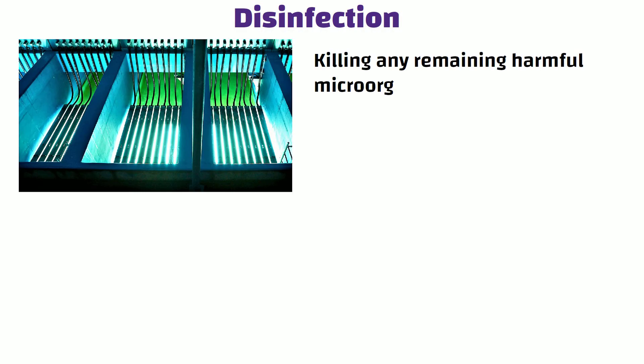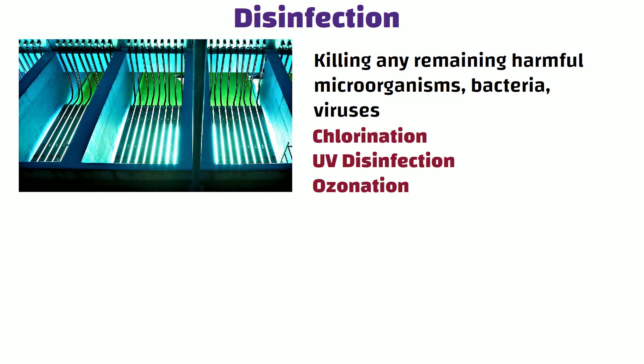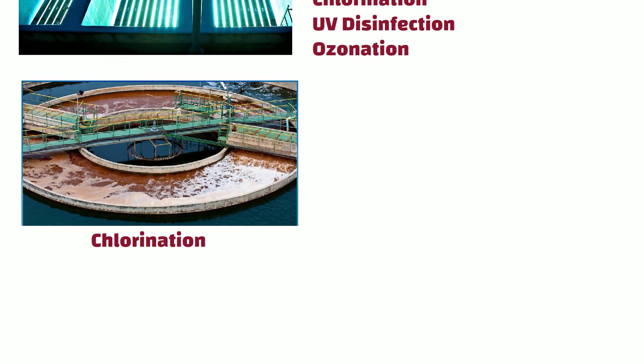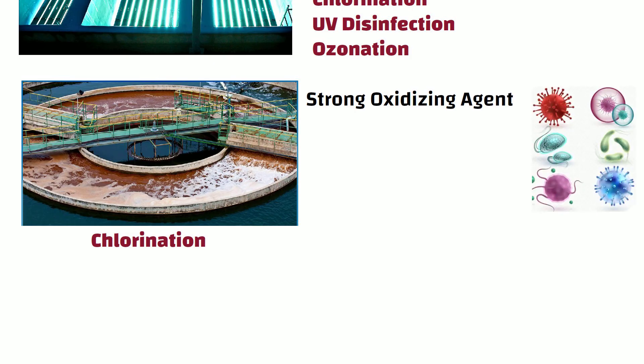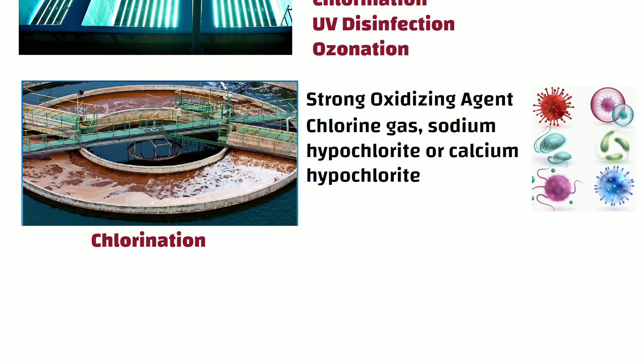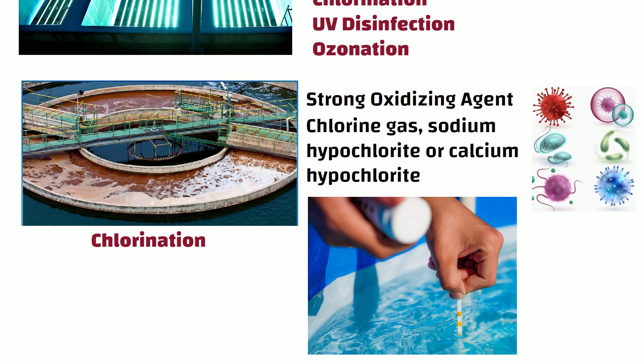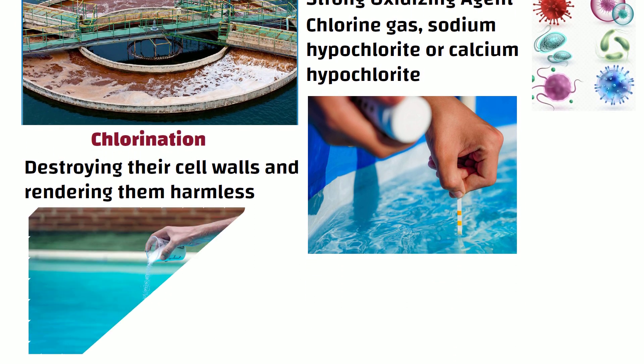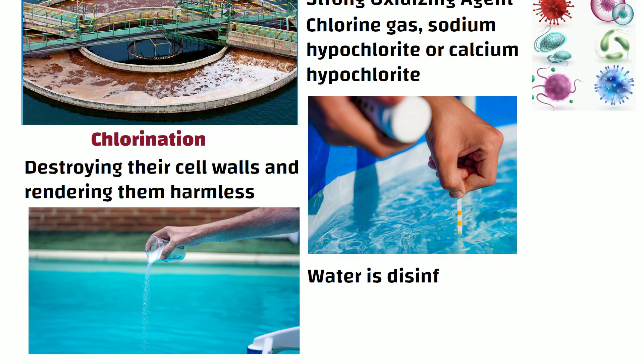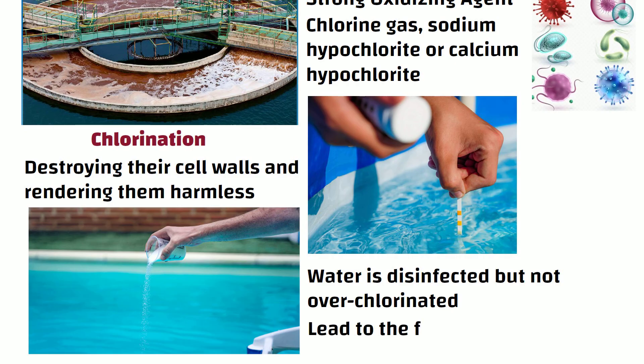Disinfection: this process involves killing any remaining harmful microorganisms, bacteria and viruses after filtration. The most commonly used methods are chlorination, UV disinfection and ozonation. In chlorination, chlorine — a strong oxidizing agent — is added as chlorine gas, sodium hypochlorite or calcium hypochlorite in a controlled manner. The chlorine reacts with microorganisms, destroying their cell walls. The amount of chlorine is carefully controlled to ensure the water is disinfected but not overchlorinated, which can lead to harmful by-products.